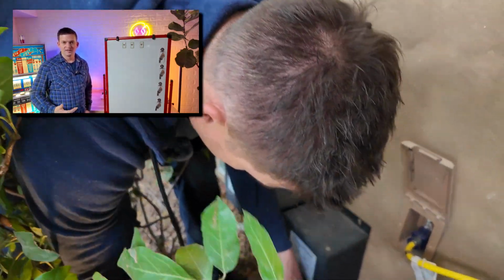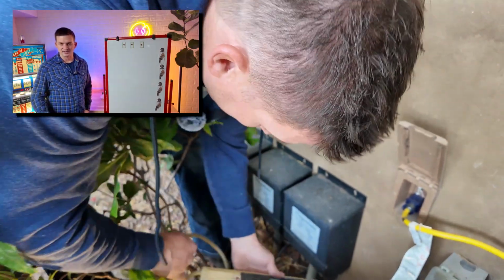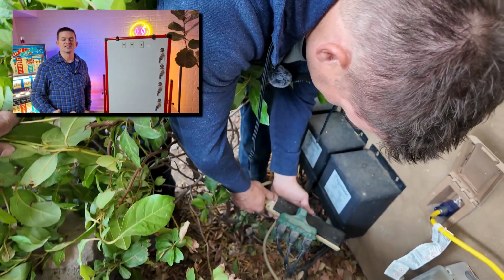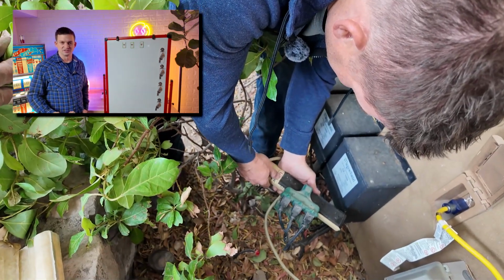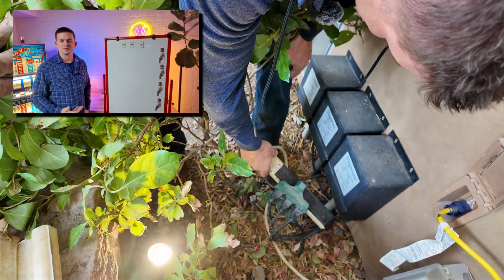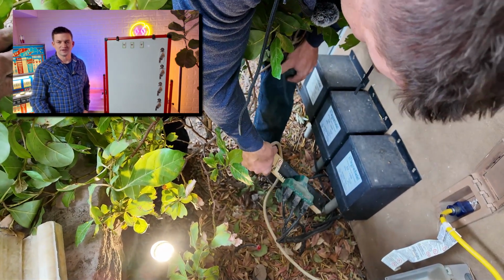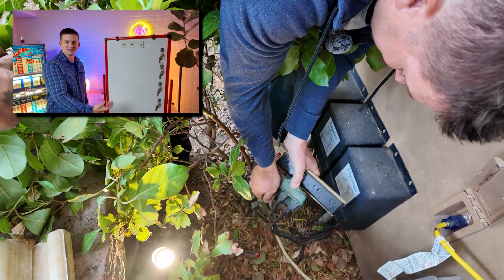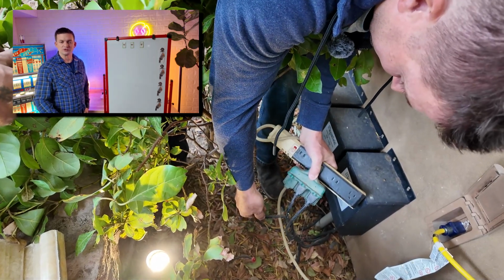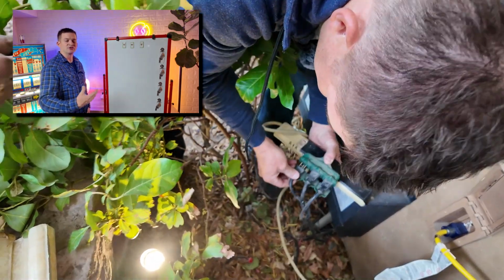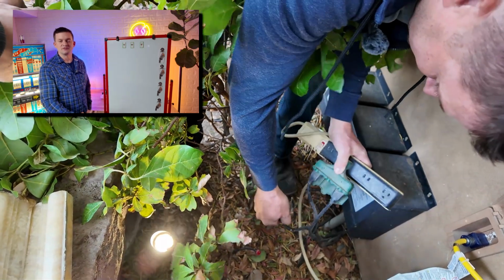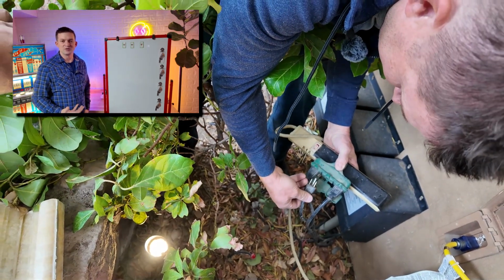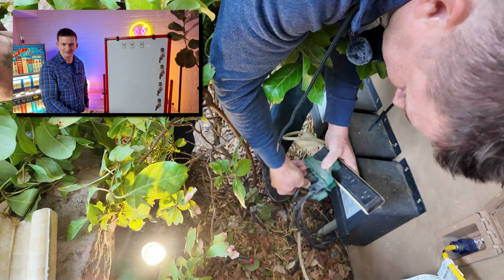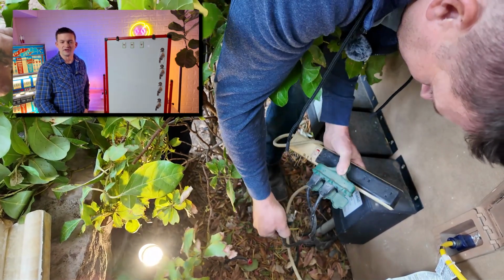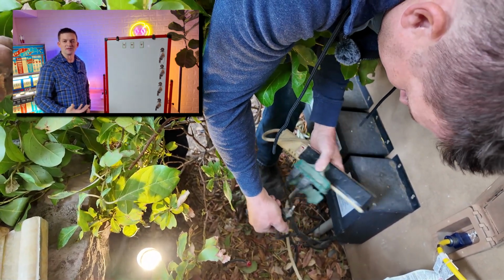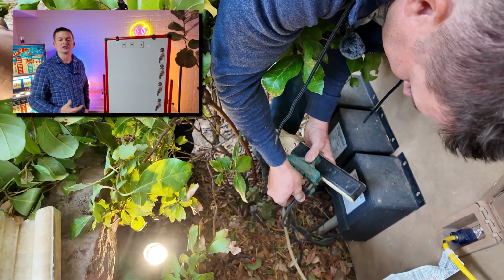we're dealing with here. The client already has an extensive lighting system with a lot of fixtures. The system was originally installed as a halogen system, and at some point during its life has been upgraded to an LED system. The transformers were left intact, as well as the wiring and the infrastructure underground. The halogen fixtures were removed and replaced with LED fixtures. This means that we've got a lot more transformer capacity and a lot more wire in the ground than what is actually needed to power the amount of wattage that the system is currently consuming.